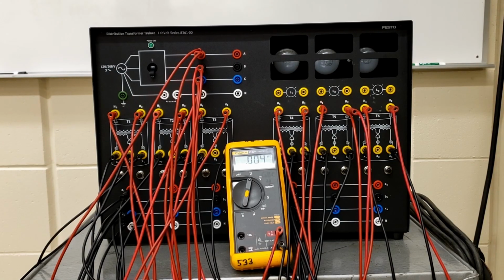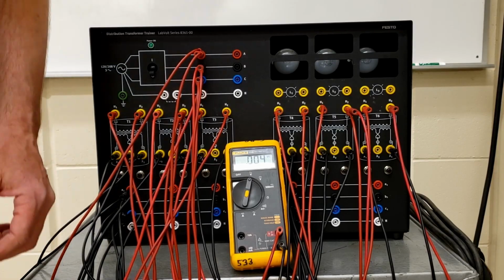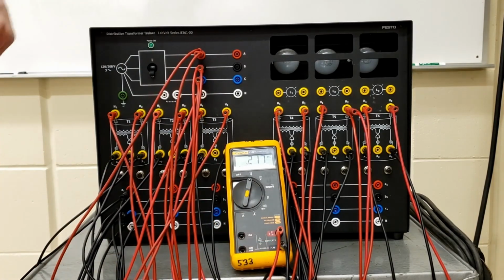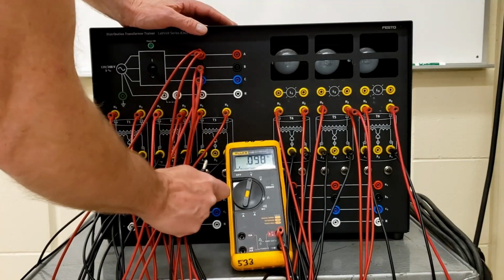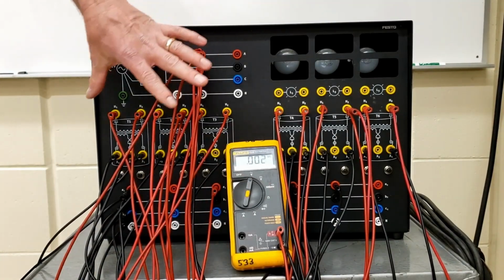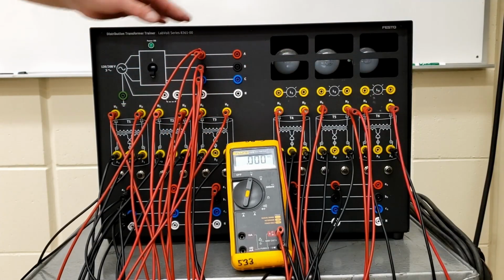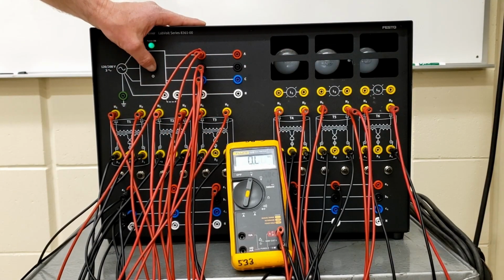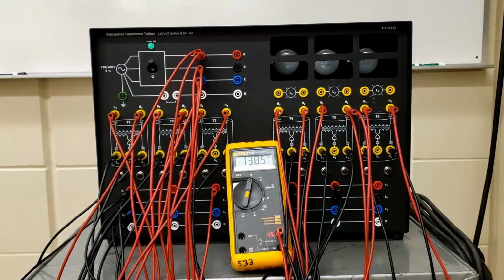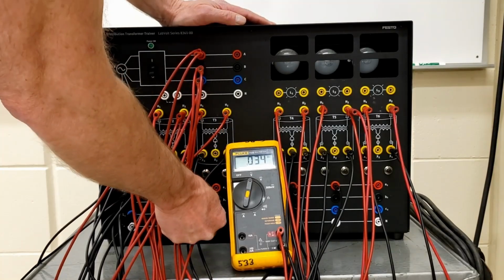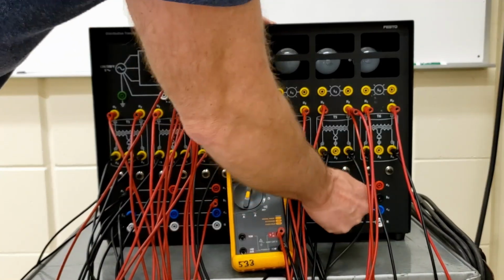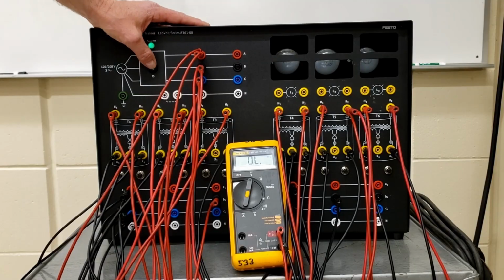Okay, and now what are we testing out between these guys? Turn on the distribution transformer and determine the voltage between lines A1 and A2, B1 and B2, C1 and C2. Okay, let's take a look. So A1, A2, so we're now comparing the two adjacent bus bars. This one's at a 30 degrees phase shift, this one's at a 210 degrees phase shift. Okay, so the voltage between those two lines is 138 volts. Between B1 and B2, we've got an identical voltage of 138 volts.